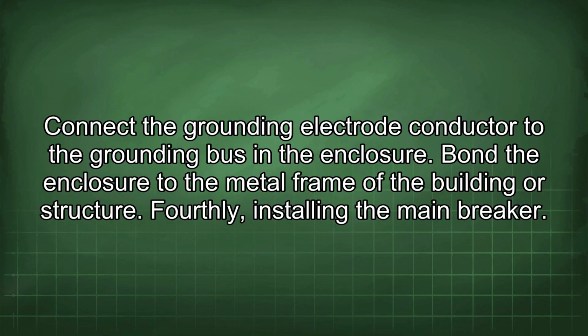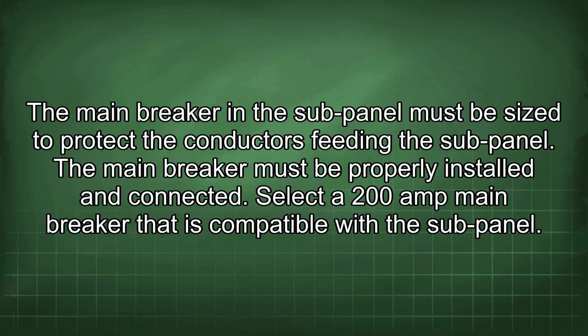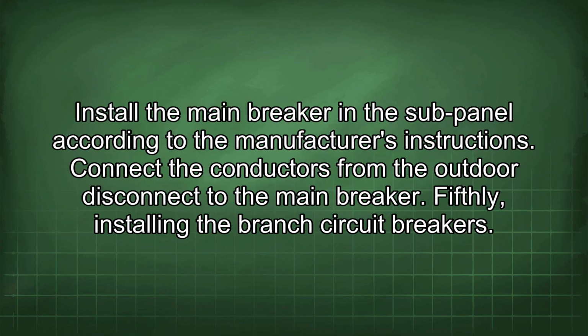Fourthly, installing the main breaker. The main breaker in the sub-panel must be sized to protect the conductors feeding the sub-panel. The main breaker must be properly installed and connected. Select a 200 amp main breaker that is compatible with the sub-panel. Install the main breaker in the sub-panel according to the manufacturer's instructions. Connect the conductors from the outdoor disconnect to the main breaker.